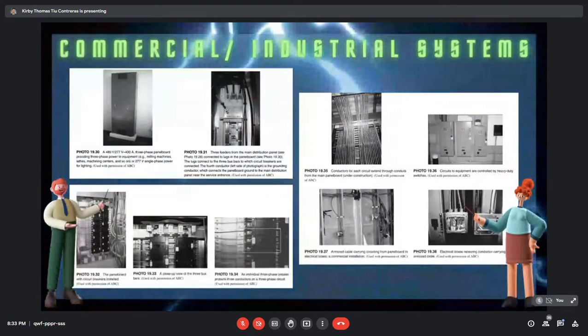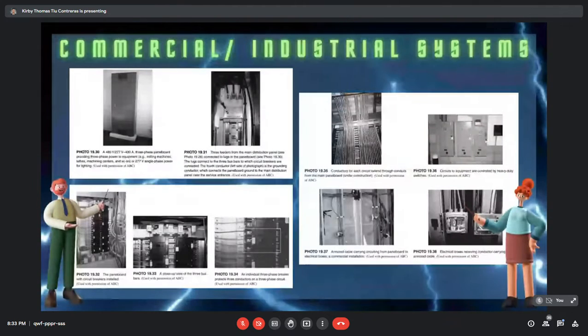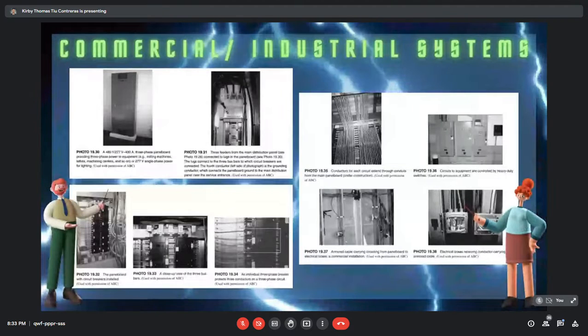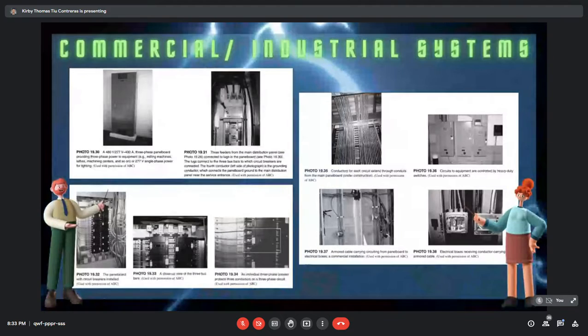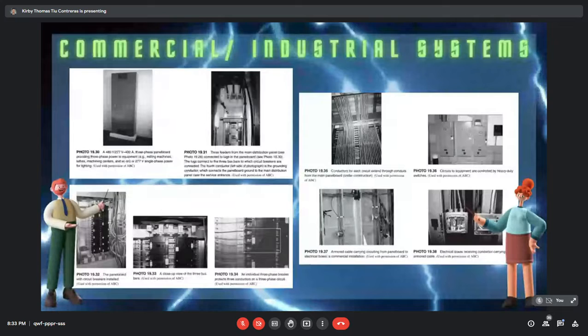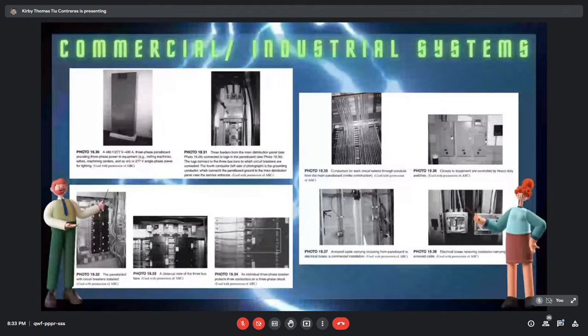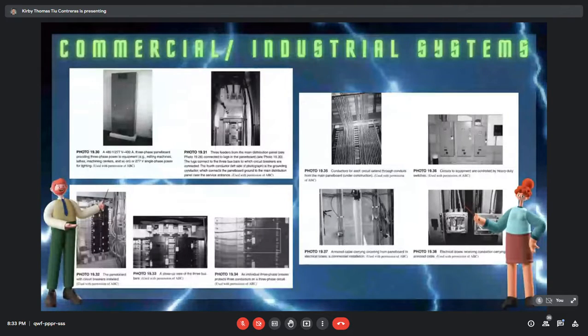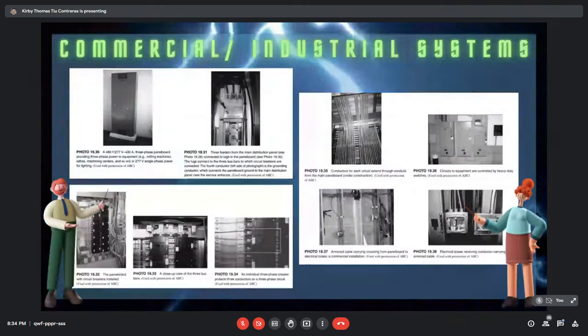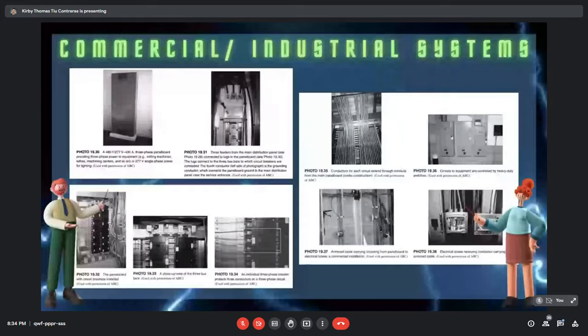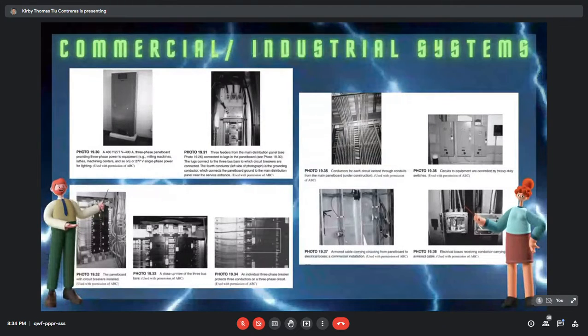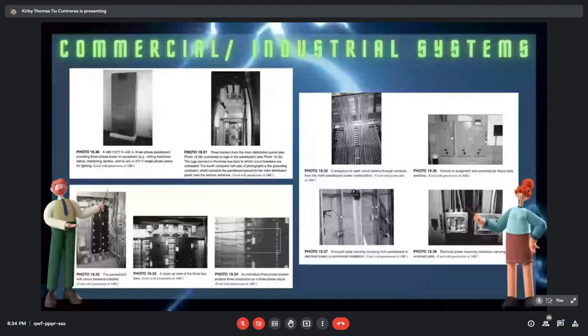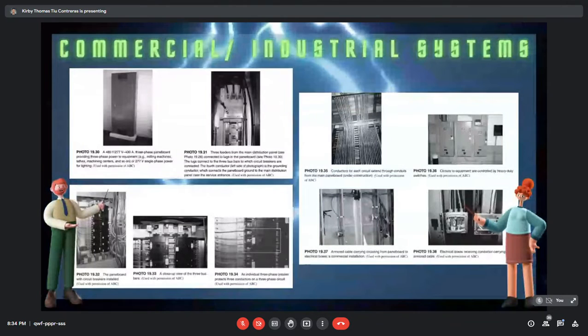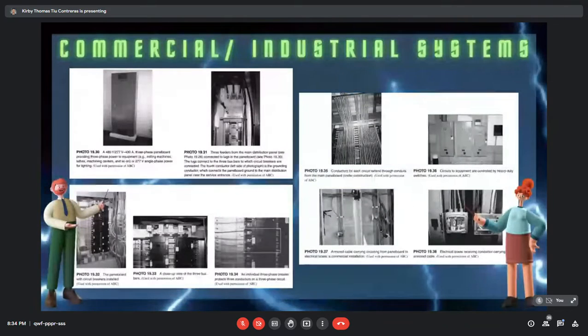The panel board also provides single-phase power for lighting at 277 volts. In the next photo, 3 feeders from the main distribution panel are connected to lugs in the panel board. The lugs connect to the 3 bus bars to which circuit breakers are connected. The fourth conductor, on the left side, is the grounding conductor, which connects the panel board ground to the main distribution panel near the service entrance.